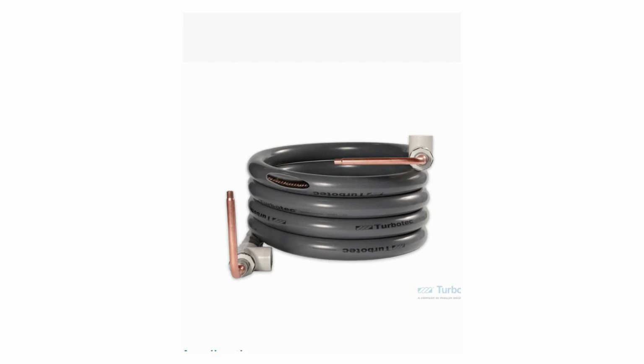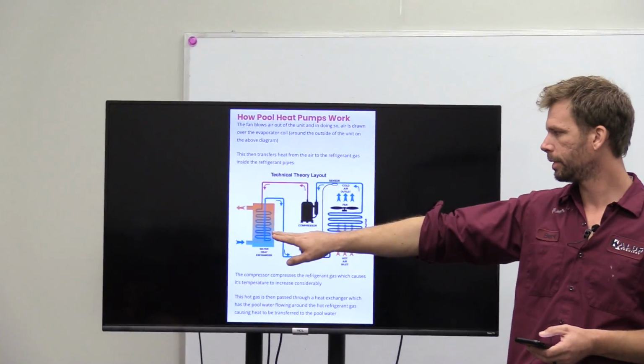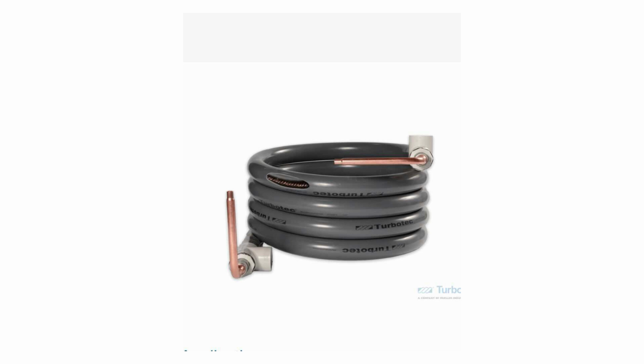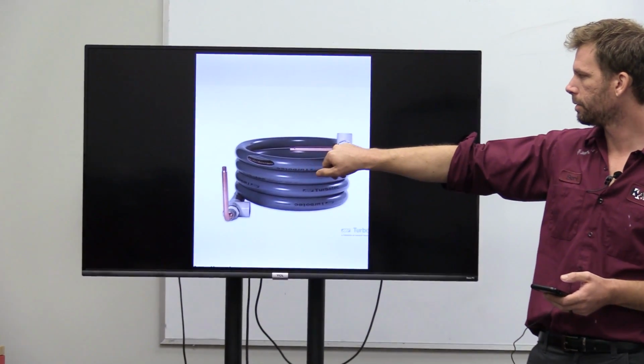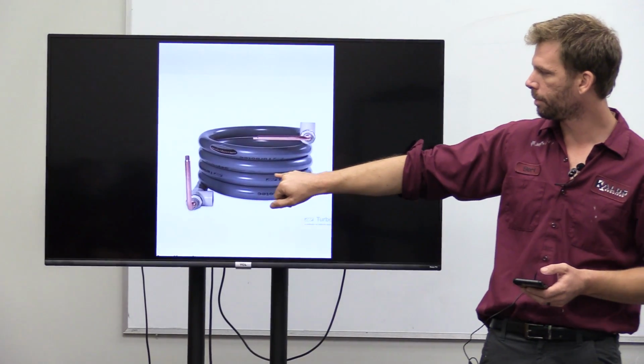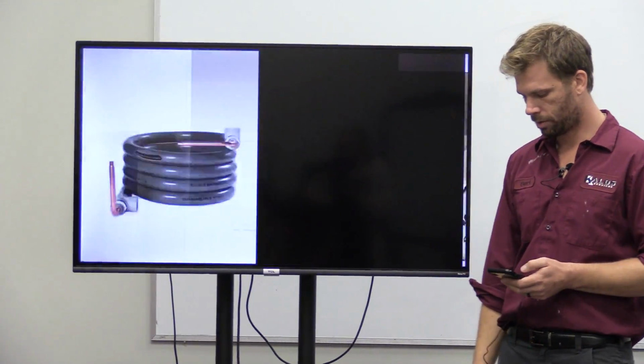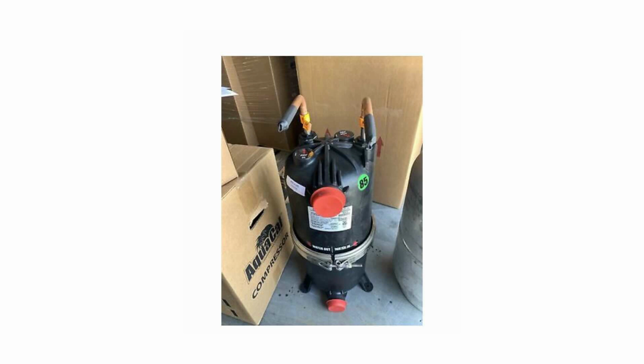Let's see, this is a heat exchanger. So every pool system, whether it's gas or refrigerant, will have some system like this. And that's what you see here doing the condensing job, right? So you have a water hookup coming in, water hookup going out, and your refrigerant lines, which in here just circle through the middle of that water pipe, as you can see on here. So this is another common style. This is a heat exchanger. And this is basically the only element that's going to be different than your typical AC system. This is your outdoor unit function on an AC system, the condenser. And then all the other components in there electrically are going to be pretty much the same.